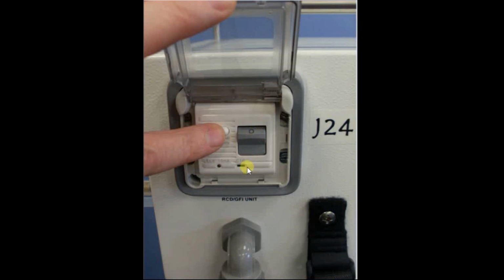And do remember that even though this is off, does not mean that the machine will not work, because it will run on batteries at this point. And the takeover is automatic. There's nothing you need to do. If the mains fails at any point during an anaesthetic, then the switchover is automatic and the machine will continue to function exactly as it was when the mains went off.